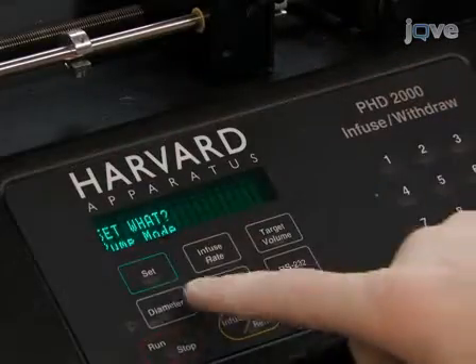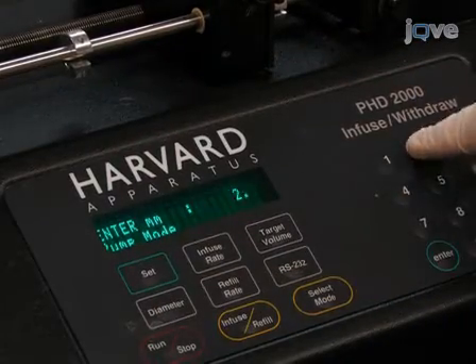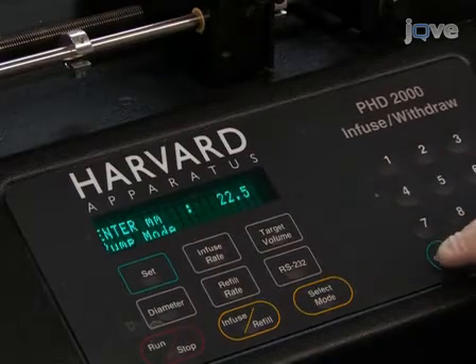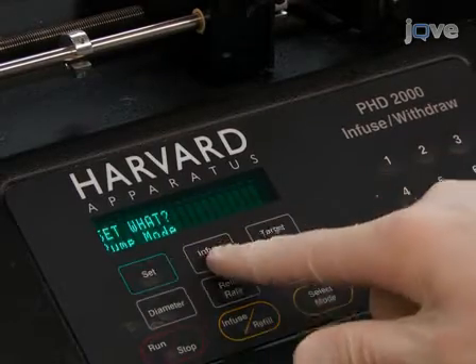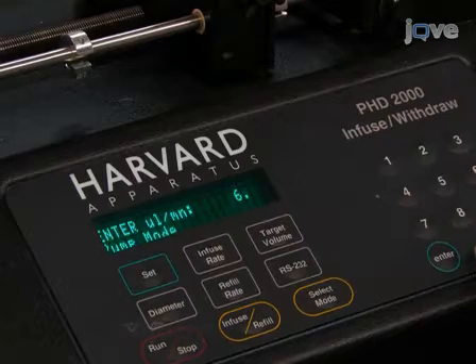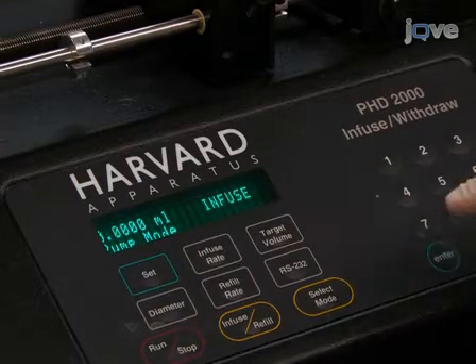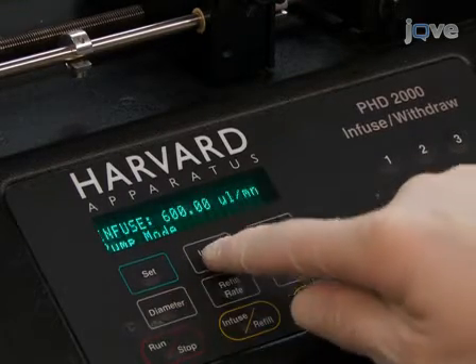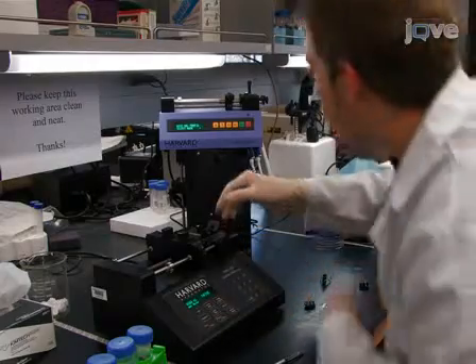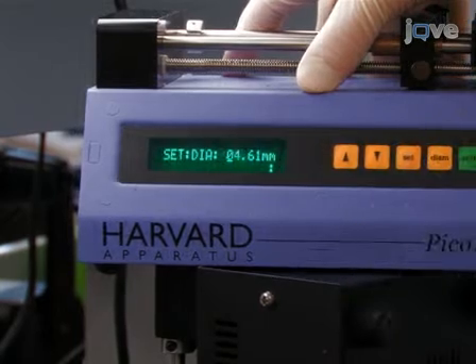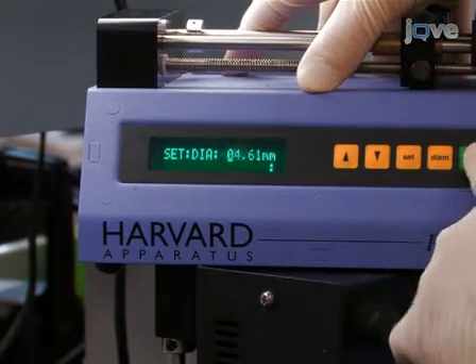Start calibrating the syringe pumps with the large Harvard syringe pump, setting the diameter configuration to 22.5 mm and the flow rate to 600 microliters per minute. For the small Harvard syringe pump, set the diameter configuration to 4.61 mm and the flow rate to 20 microliters per minute.